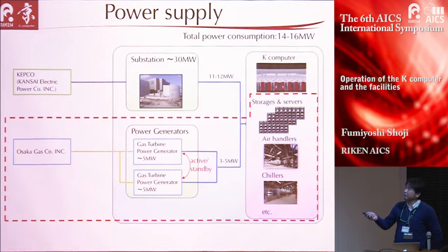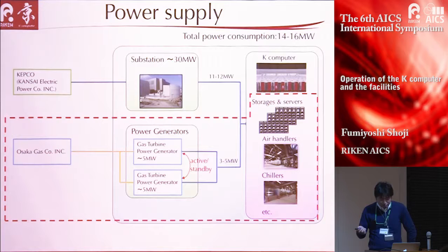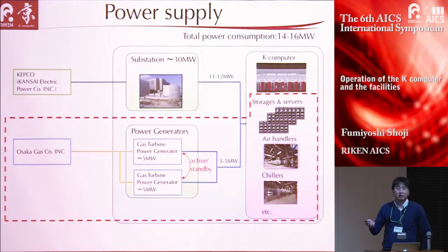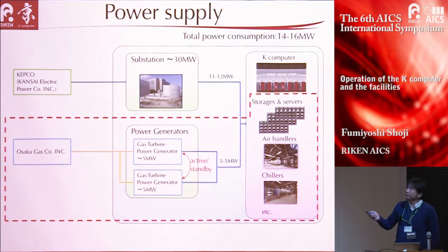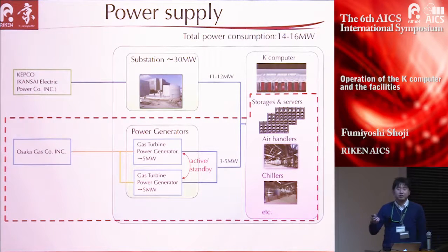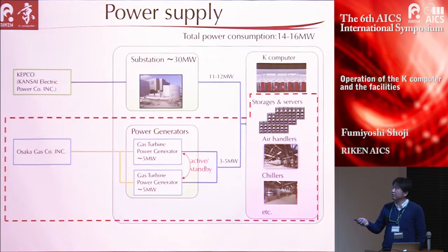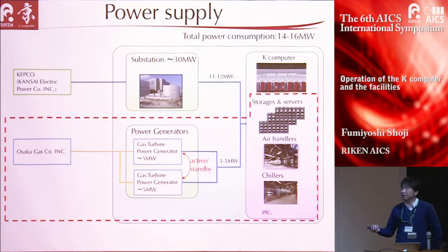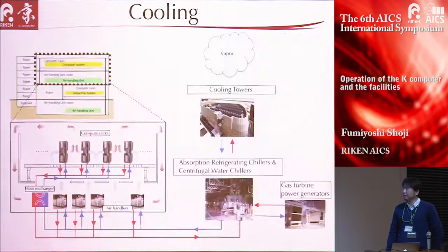The generator also works as backup power supply for servers and storage when a power outage occurs. However, the K-computer consumes really huge power, so the power generator cannot cover the K-computer. We gave up trying to save K-computer when a power outage occurs.